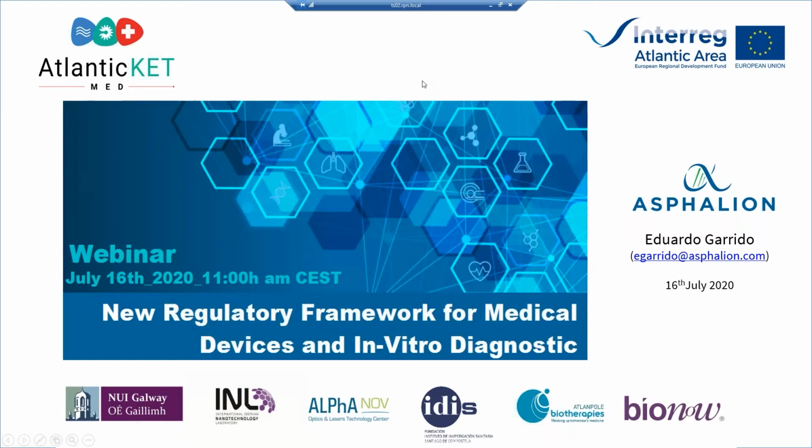It's important to demonstrate that the system can work when it's assembled. It's not the same as certifying the individual parts. Obviously, if you test several parts separately, then you don't have to repeat everything with your assembled device, but you have to demonstrate compatibility.